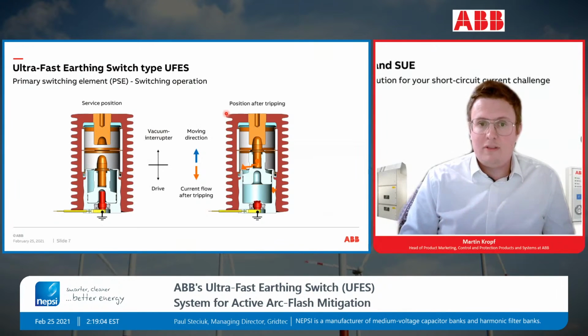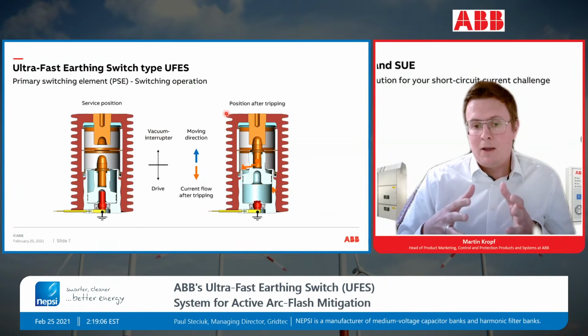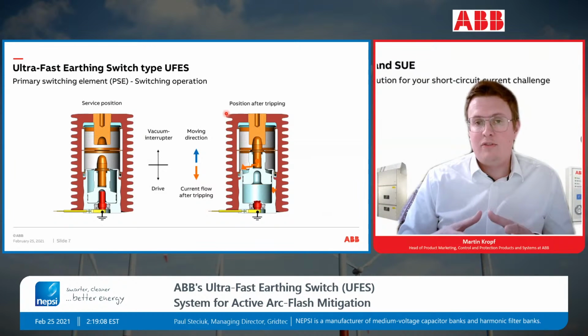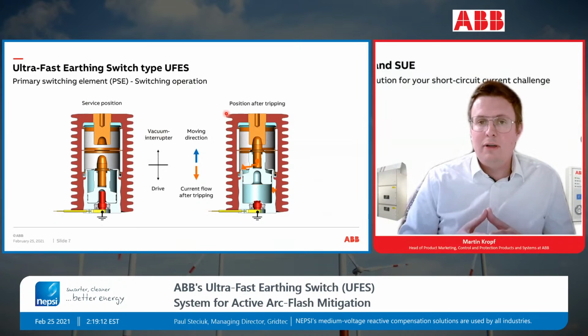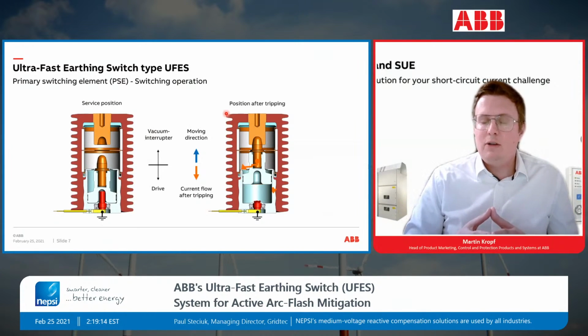The fault happened, you go to site, first you have to locate the fault - I think we'll see this also later on another video - isolate the defective device, remove the rat which was walking around in the switchboard, and then change the 3 primary switching elements.